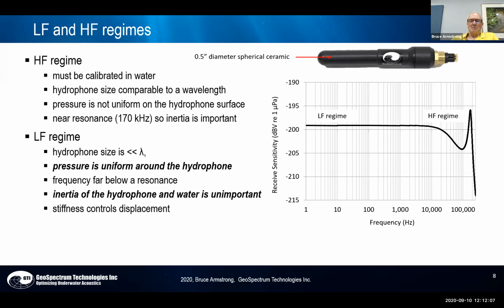But then you get the low frequency regime, and that's where you can do your calibrations in air if you wish. And you see the low frequency regime is characterized by that ruler flat response from, I graphed it here from 1 hertz, but it goes down to 0.1 hertz or 0.01 hertz, all the way up to, in this case, about 10 kilohertz. So in the LF regime, the hydrophone size is far smaller than a wavelength, and what that means is that the pressure is uniform around the hydrophone. All parts of the hydrophone see the same pressure. And the frequency is also far below a resonance. What that means is that the mass of any component in the hydrophone or the water is not important. The forces required to stress the ceramic are completely controlled by the stiffness of the ceramic, and there are no inertial effects. So if you're down at the low end of the LF regime, you can calibrate in any fluid that applies a uniform pressure.